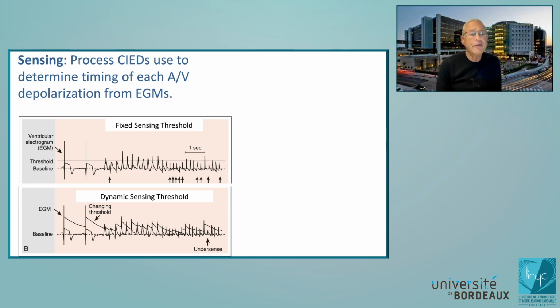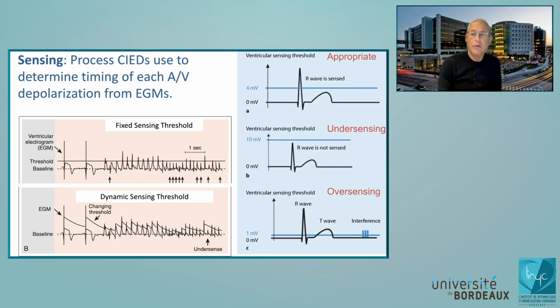The definition of sensing that I use is that it's the process by which defibrillators or pacemakers determine the timing of each actual atrial and ventricular depolarization from the electrograms. So how does this actually work? Well, I think Dr. Strick probably went through this with you, but we have what's called a sensing threshold. So the device waits until the electrical signal exceeds this sensing threshold, and then it puts down a timing marker. And that is what we refer to as a sensed event.